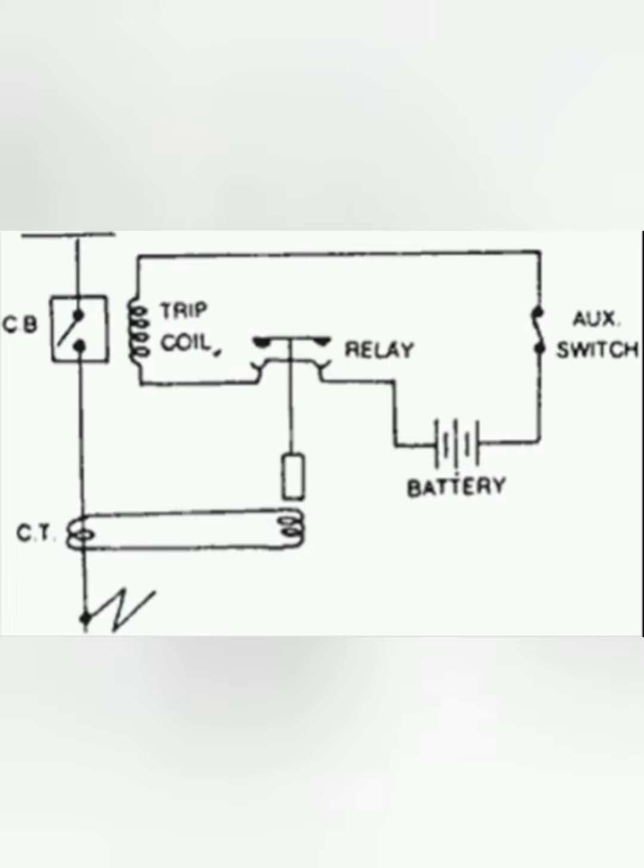In any chance, if there is any fault current or a value persisting over your protection level current, your relay automatically senses it and initiates the trip to your circuit breaker. Then the circuit breaker gets opened. So this is the basic overview of circuit breaker operation. In this diagram it is totally carried out by electrical operation only. Actually we can also operate the circuit breaker manually, which means mechanically.